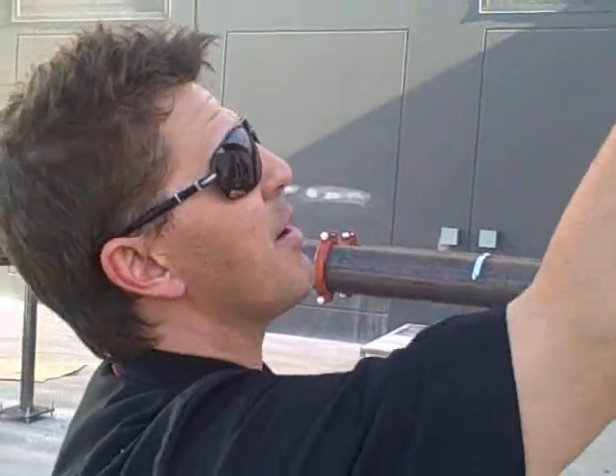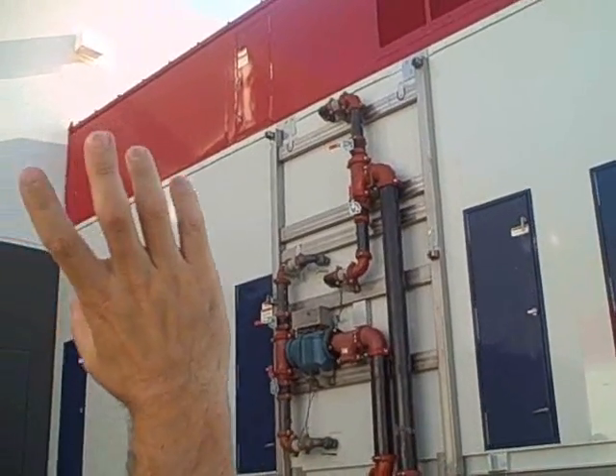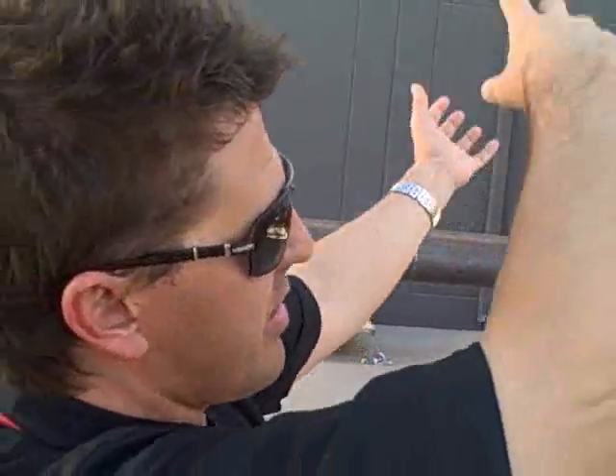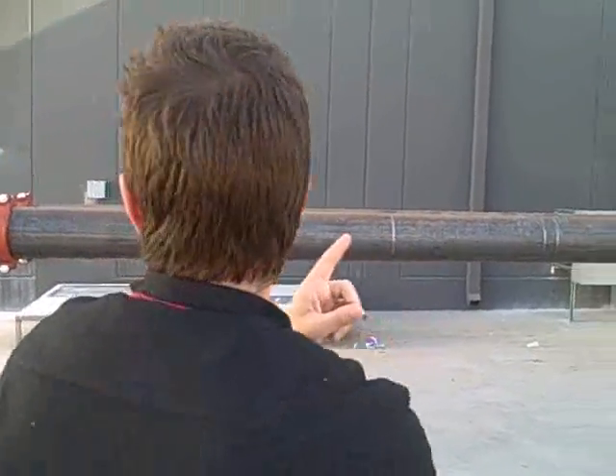In terms of wet bulb temperature and outside temperature, and then on the top the big red sections are plugged directly into the heat chamber in the building and they can expel the heat directly outside if needed. The whole system can seal itself and run 100% recirculation. It can also be sealed down — if there were ever a biological attack somewhere in the city, we can seal the unit so you're not bringing in any outside air. All part of the design.